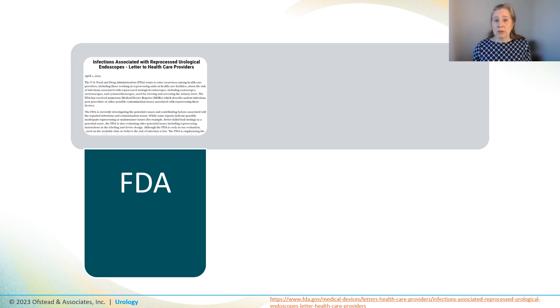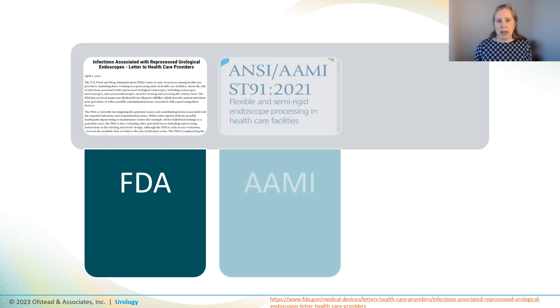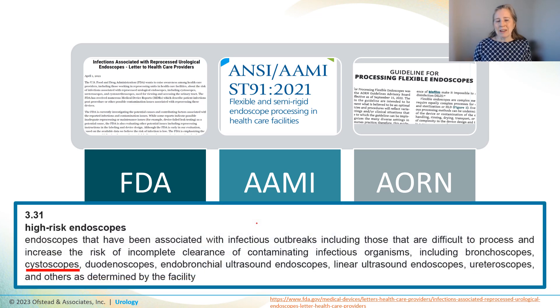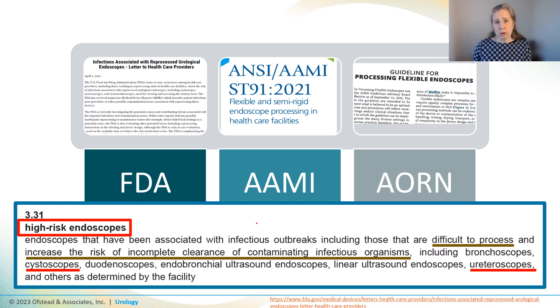The FDA also said that patients should be informed of the risk associated with procedures involving urology scopes. Since then, AAMI and AORN have released new standards that are more stringent, classifying urology scopes as high-risk scopes because they're especially difficult to process — increasing the risk that germs are not completely removed. They recommend extra steps be taken to ensure scopes are clean before attempting sterilization.